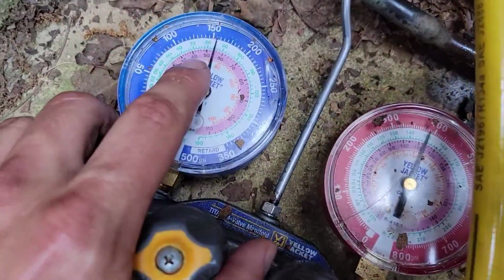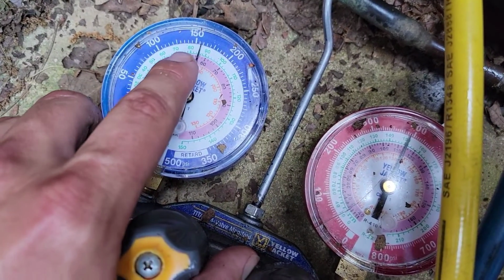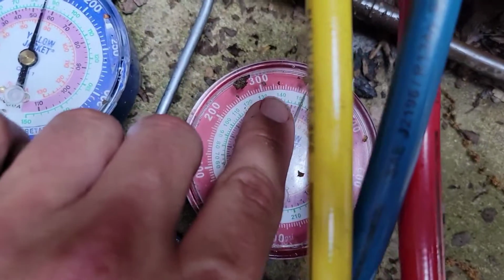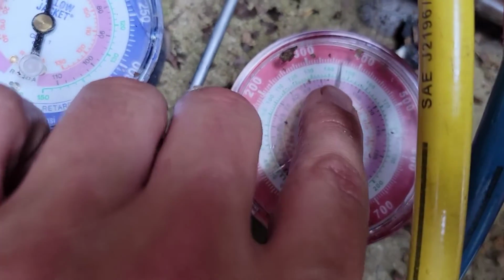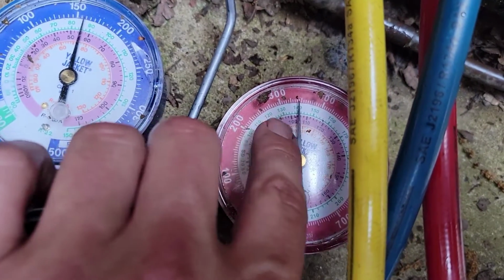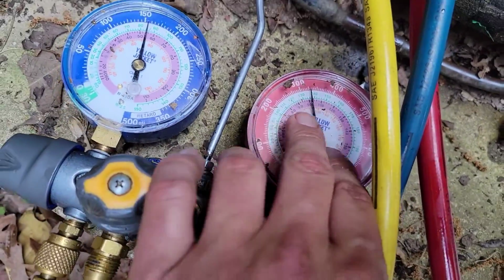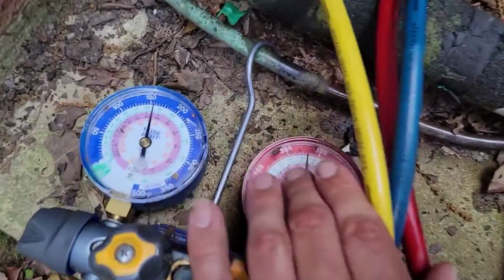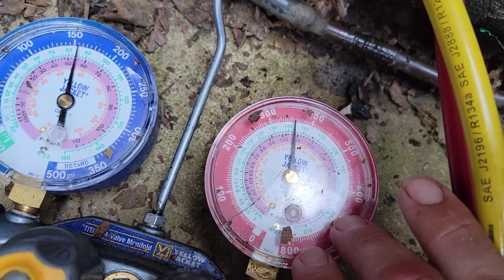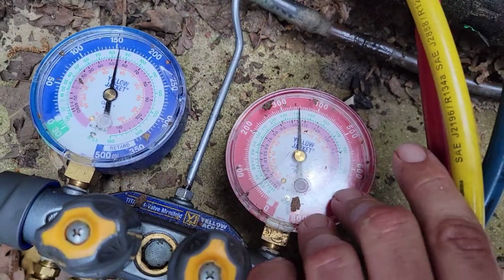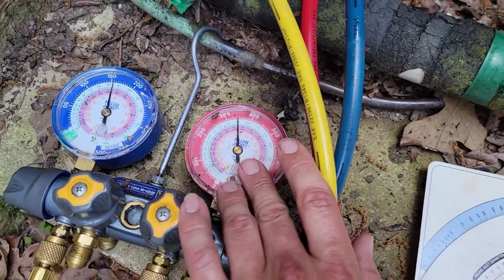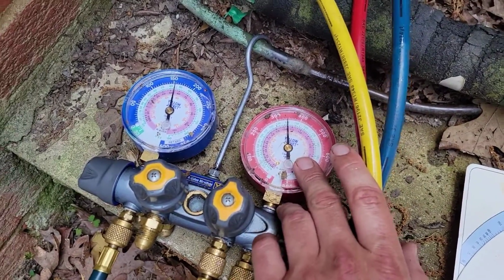Typically, I'm going to run, depending on indoor and outdoor ambient conditions, around 125 and then about 325, 350. Look what's happening. Up and down, up and down. This thing is moving like it's going crazy. Look at this. Back up, back down. That's the TXV. Okay, that's what's causing that. Our metering devices. I'm going to show you what's going on with this job. Liquid line's not warm and the vapor line is nice and cool.